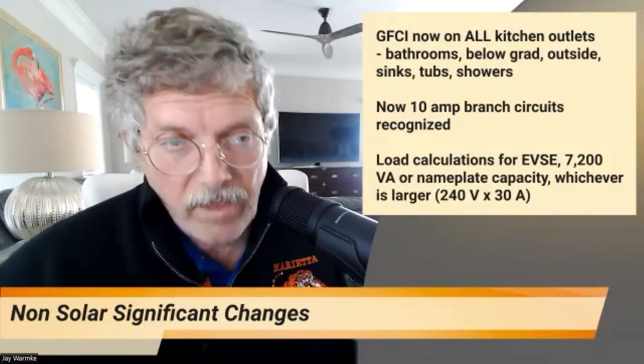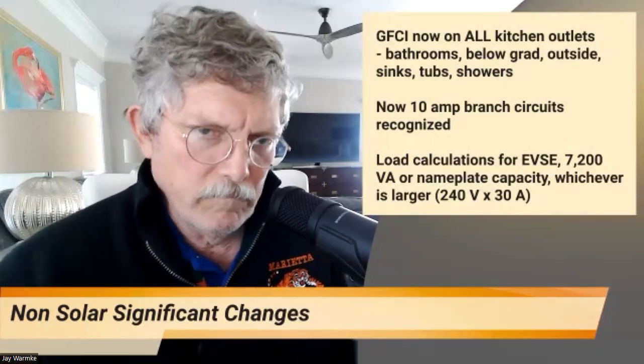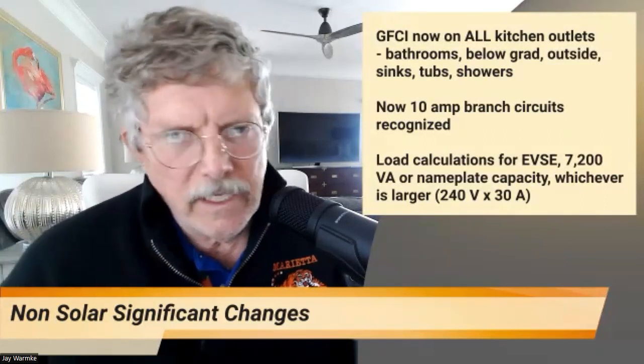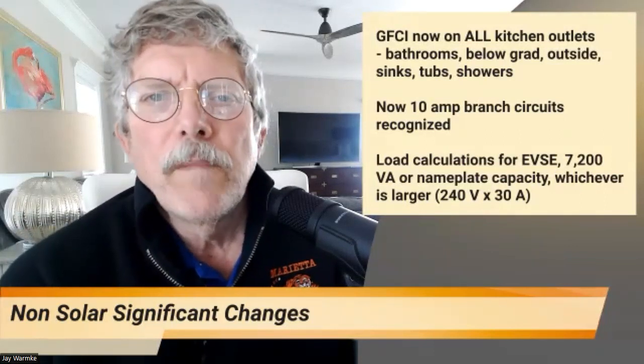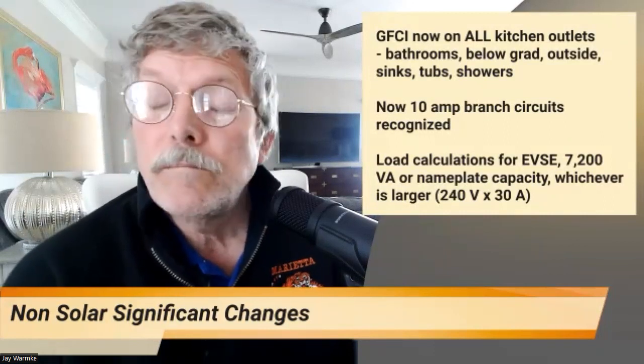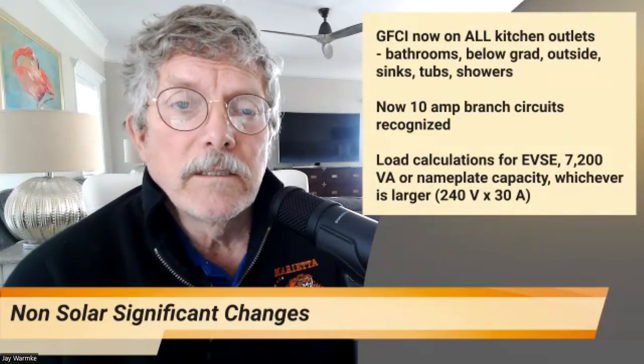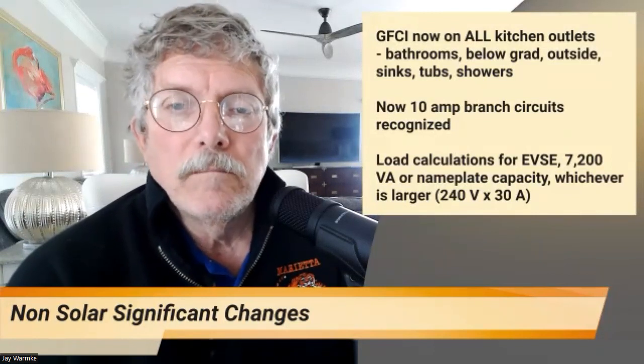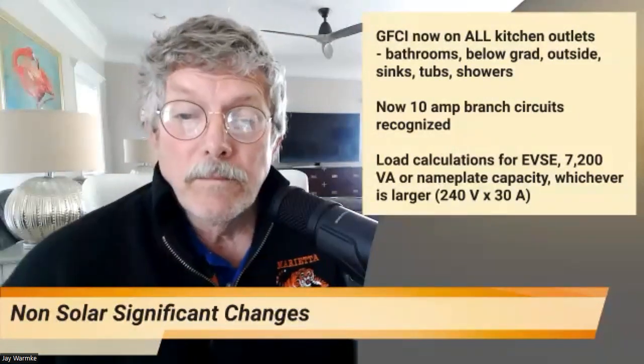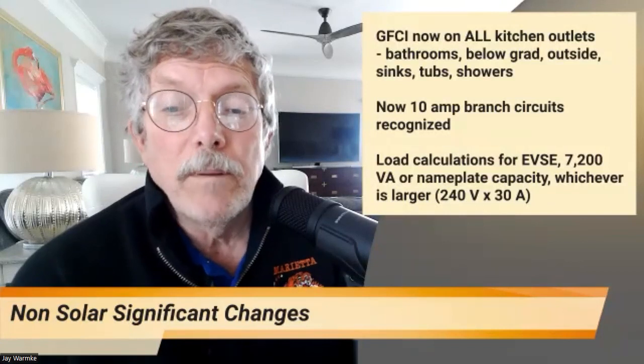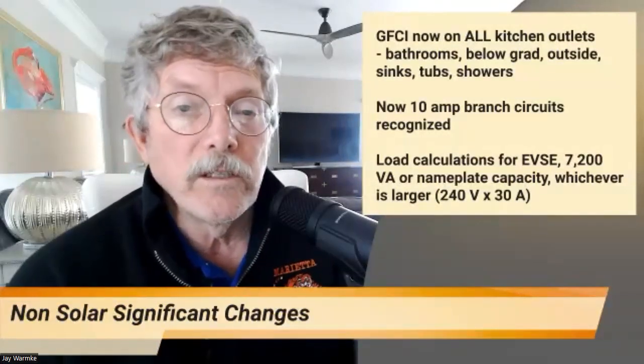So basically they're saying if it's a 240 volt charging station, minimum ampacity is going to be 30 amps. But if you're putting in, for instance, the Ford Lightning, that has an 80 amp charging station. So you'd have to have an 80 amp circuit for that at minimum. So they're beginning to define that. I suspect that's going to keep going up, but at the moment, smallest you can do is 30 amps. So if somebody has one of those EVSE equipment that is rated for 16 amps, which you do find some level 2 chargers for, the circuit wiring and the breaker size and everything had to be rated at the 30 amps, 32 amps. Yeah.